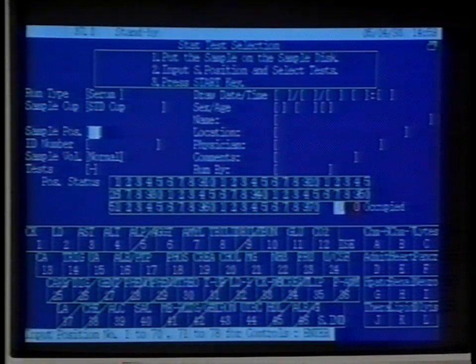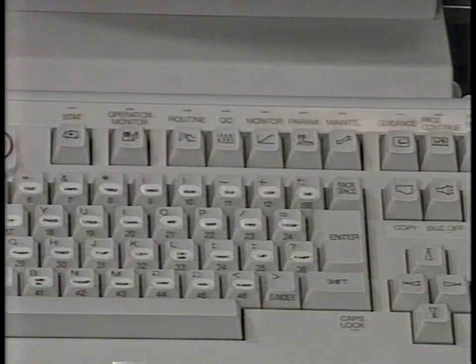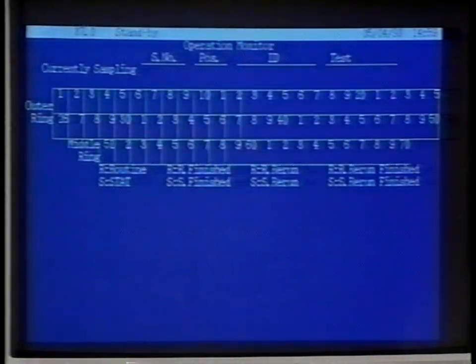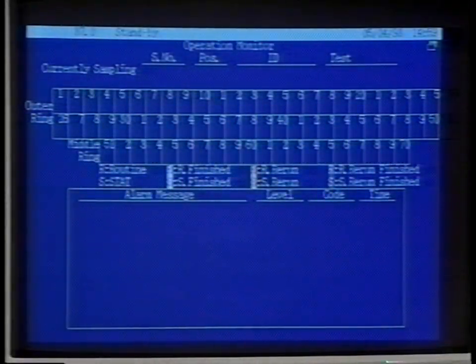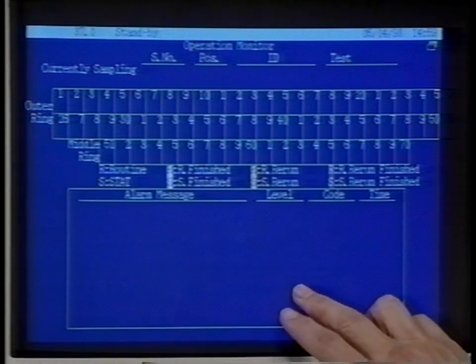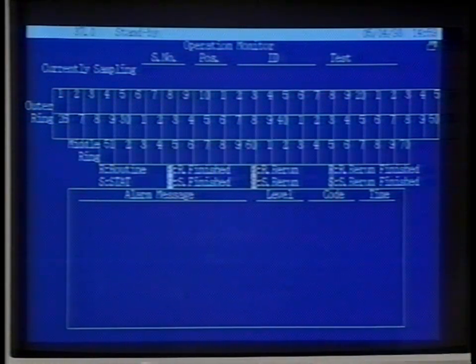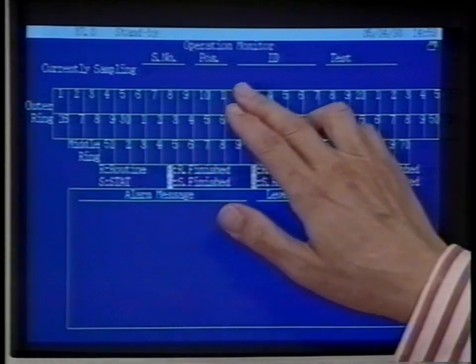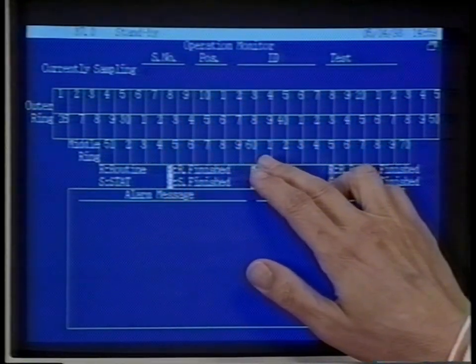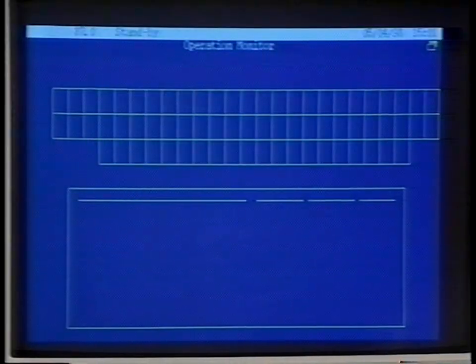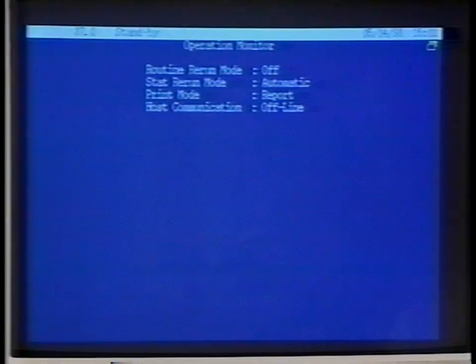The Operation Monitor job is selected by pressing this job key. The Operation Monitor screen allows you to monitor a number of analyzer conditions, for example, the current run conditions and any instrument alarms. The sampling grid tracks samples as they move through the various analytical unit processing stages. There are 2 pages for this screen. Press the guidance key to view the second page of the screen.